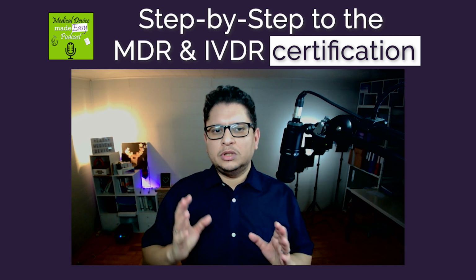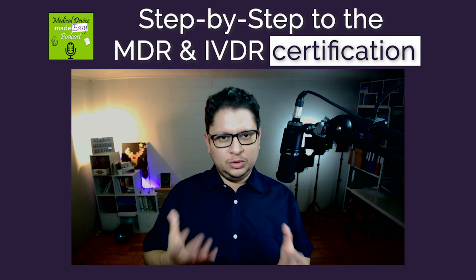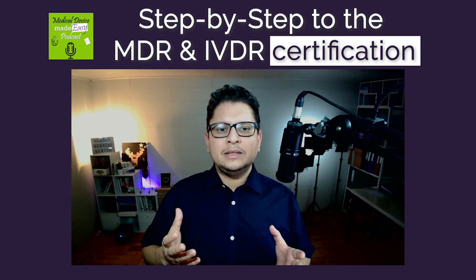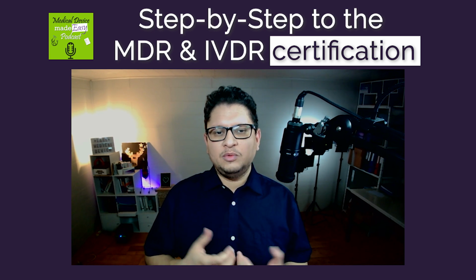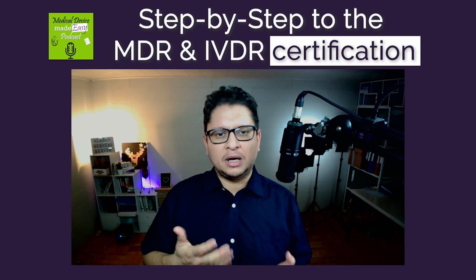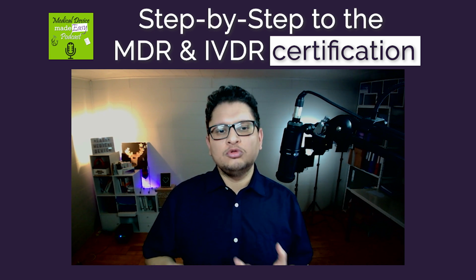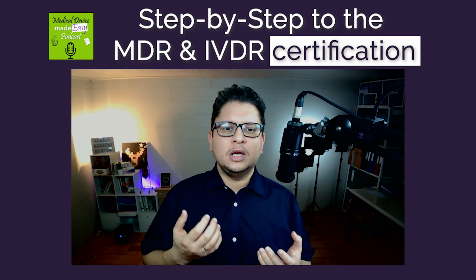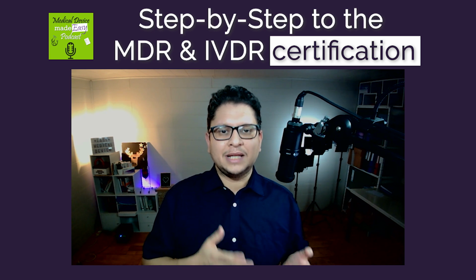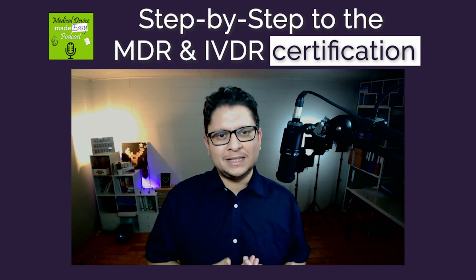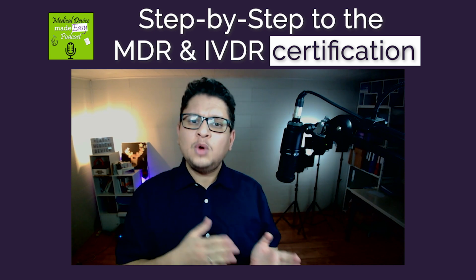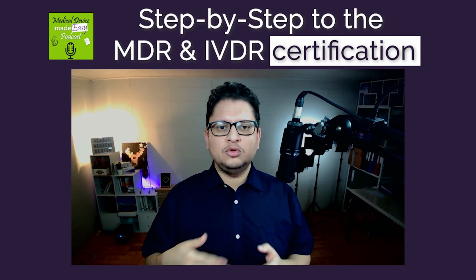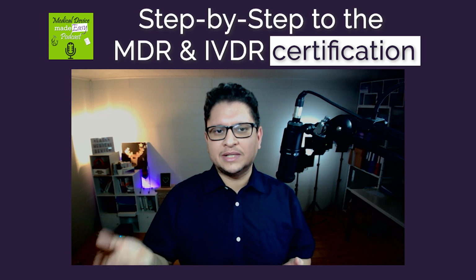Okay, so then you have this situation where you need a quality management system, and under the EU MDR there is Article 120 Part 3, which provides some rules in terms of the transition period. So as I've said, you have some manufacturers that have to get certified by the 26th of May 2021, and you have others that can still continue under the MDD until a certain date.